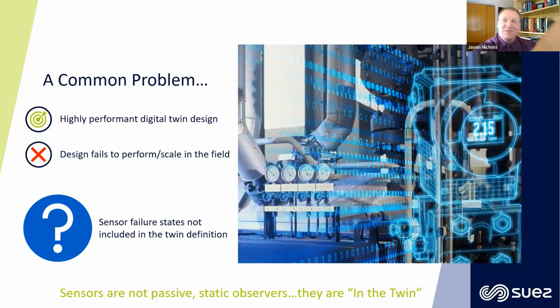There were many reasons, but one common reason was that failure states of the sensor were not included in the twin. And the failures weren't just that a sensor completely failed, giving a stuck value or a physically unreliable value—it's that the sensor gives a value slightly off from what it should be, for reasons like improper installation, calibration drift, bias drift, or an event that causes it to start reading differently. These things are not included in the state space of a typical digital twin. And if you're not careful when doing continuous learning of a living digital twin, you'll learn the error right into the model, and it will drift further and further from reality.